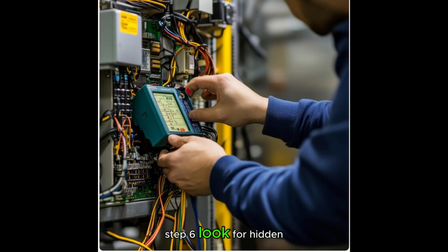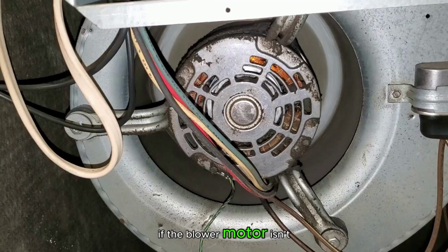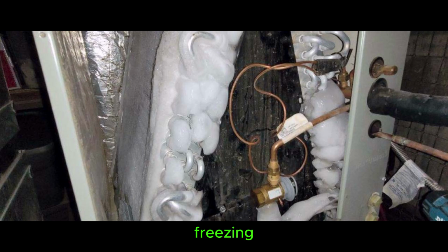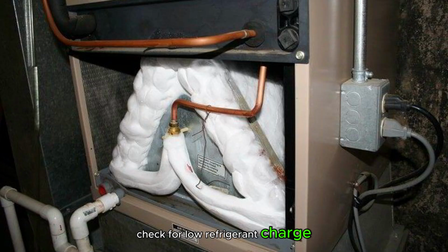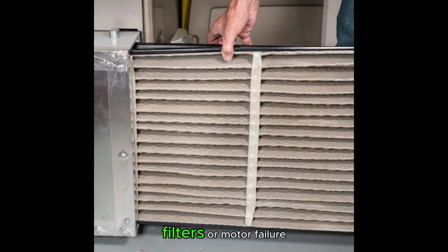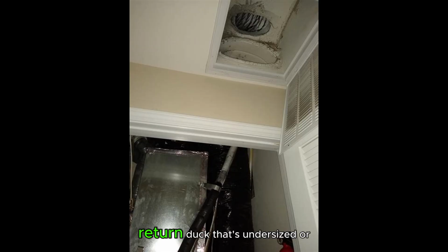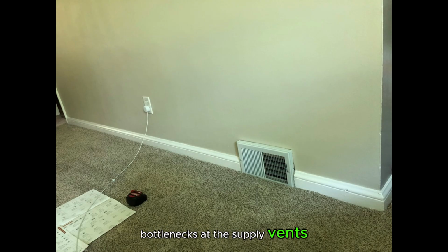Step 6. Look for hidden clues. If the blower motor isn't turning on, it may be burned, or the relay isn't working, or the thermostat isn't sending the G signal. If the evaporator coil is freezing, check for low refrigerant charge, low airflow due to dirty filters or motor failure, return duct that's undersized or blocked, bottlenecks at the supply vents, which can cause sweating in certain ducts. All of these issues can drop pressure and cause the coil to freeze.